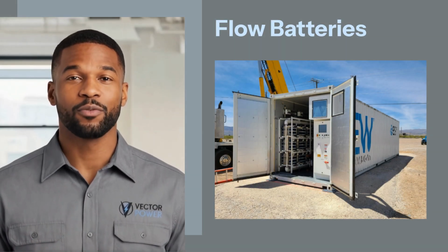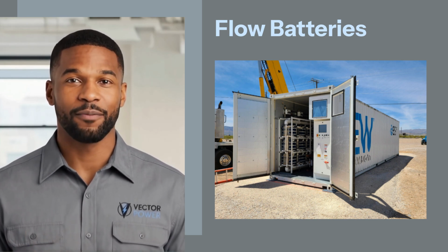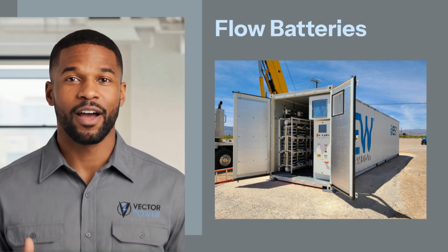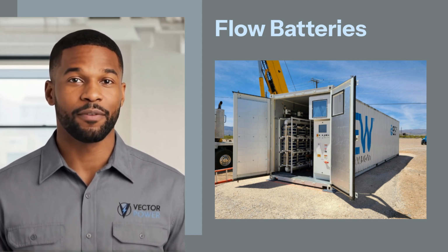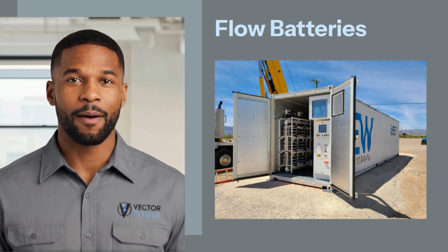Flow batteries are well suited to long-duration applications because power, stack size, and energy tank volume are decoupled. They offer excellent cycle life and can be discharged to 100% depth of discharge, but they require larger footprints and balance of plant equipment, such as pumps and controls.